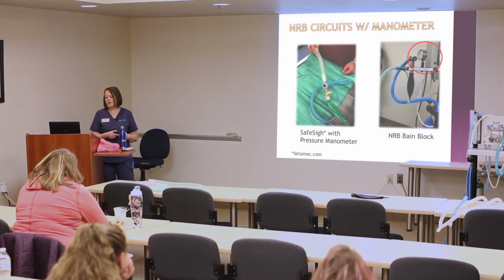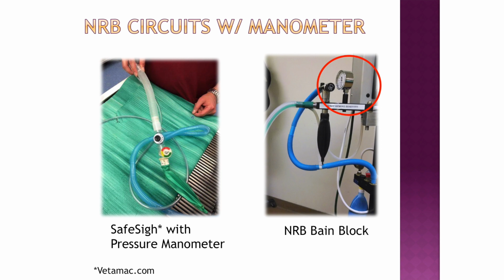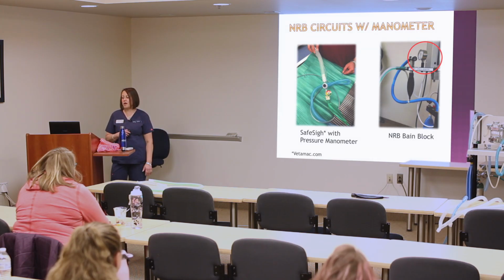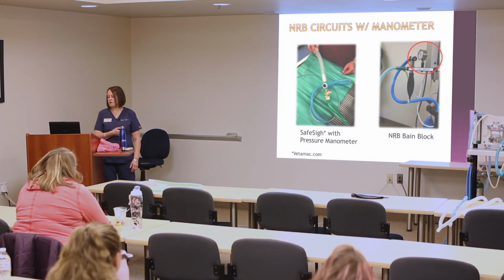So this is all we have around here now, the SafeSigh with a pressure manometer. This is actually the pressure manometer right here. It basically is very simple. You got green for okay, yellow for caution, red for don't do that. And the non-rebreathing Bain block for the little bitty guys, we have this official system here if you're going to be doing a case for a while. It's still a non-rebreathing circuit, even though it has a coaxial hose design on it. But it has a nice pressure manometer. We can actually hook this up to the ventilator, and I can show you how to do that if you're interested.